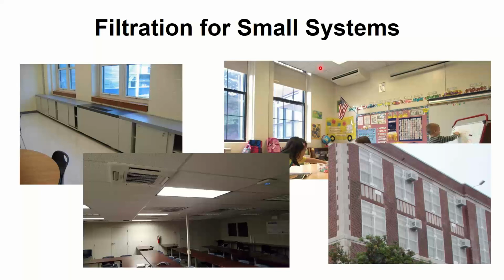So you can't really upgrade the filtration at all on those two. And then some of you may have heating-only schools, right, where you've got radiators or baseboard in each classroom to heat the school, and then you've put in small air conditioners or maybe window air conditioners to kind of temper things off in September and in May. But you really don't have an air handling system at all—you have none of these things. In the wintertime, you don't have any airflow, zero fresh air unless someone opens a window.